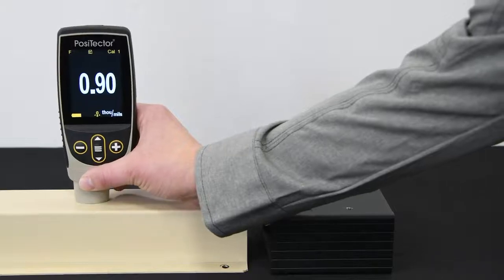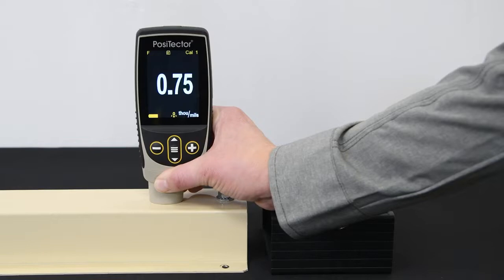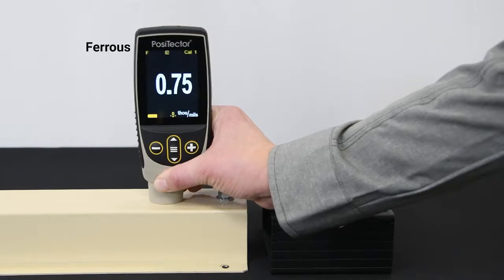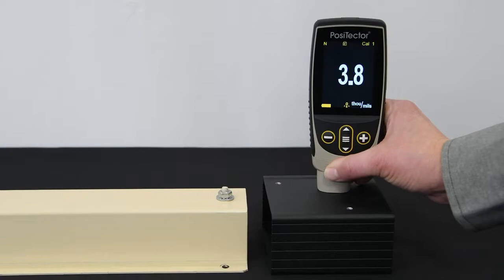Using both magnetic induction and eddy current principles to measure, the PosiTector 6000 accurately measures non-magnetic coatings on ferrous metals such as steel, and non-conductive coatings on non-ferrous metals such as aluminum, copper, and some grades of stainless steel.